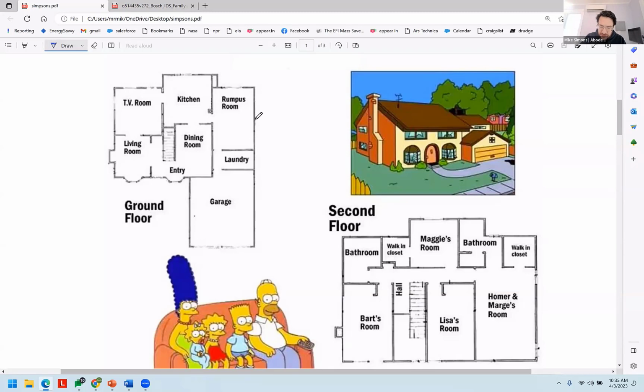In your case, the home is relatively low-load, with a total heating load of about 32,000 BTUs. So there may be a possibility of putting in a ductless unit on this side of the house and another ductless unit on that side, with two 12,000 BTU units. Depending on the upstairs, which only has a heat load of 12,000 BTUs, there could be an option of reusing the air handler up in the attic space, because one ductless unit wouldn't have anywhere close to sufficient coverage — you can't just stick it in the bathroom. So downstairs could be two ductless pieces of equipment, and upstairs a ducted piece of equipment. But it's always worth first thinking about whether ductless can work.